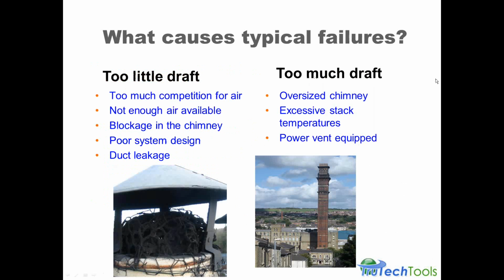And here's a couple of impactful pictures to talk about why there might be too little draft when there's a competition for the air. We talked about that very early on. Not enough air available. Blockage in the chimney, which stops the correct flow rate. A poor system design from the beginning, or perhaps even duct leakage, which causes a negative pressure zone to be established near the heating appliance.